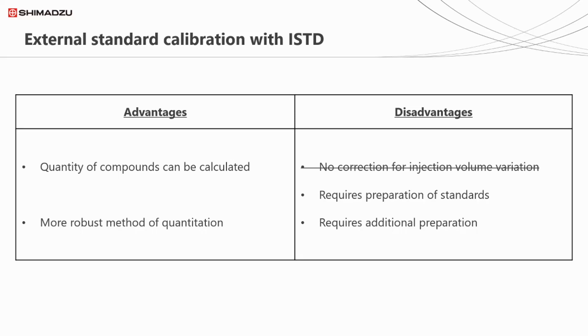This variation of the external standard calibration method therefore offers even greater robustness and more accurate results by accounting for variability in instrument response. But it does require even more preparation, as every sample and standard needs to be spiked with internal standard, and it's imperative that the amount of internal standard is either consistent across all standards and samples, or that the amount in each is accurately known and reported in the software so the calculations are performed correctly.